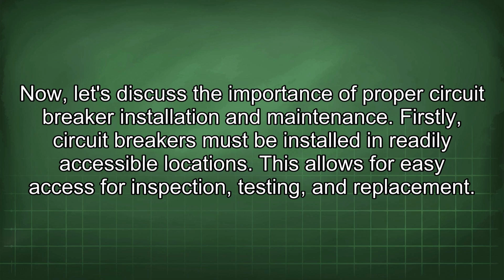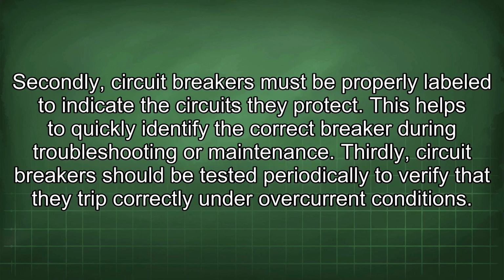Firstly, circuit breakers must be installed in readily accessible locations. This allows for easy access for inspection, testing, and replacement. Secondly, circuit breakers must be properly labeled to indicate the circuits they protect. This helps to quickly identify the correct breaker during troubleshooting or maintenance.